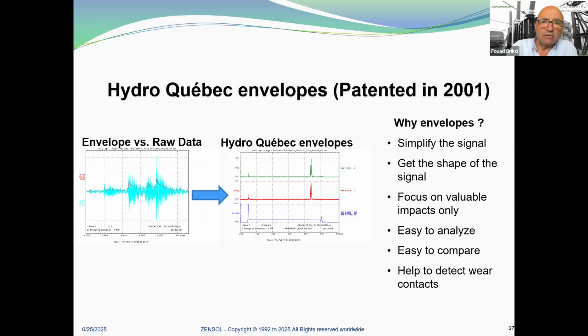Hydro-Quebec envelopes, patented in 2001. On the left, you can see the raw data of an accelerometer signal with the envelope superposed. Hydro-Quebec envelopes have been patented by Hydro-Quebec in 2001. And on the right graph, you can see the envelopes for the current and the high frequency and low frequency envelopes. So why envelopes? It simplifies the signal, gets the shape of the signal, focuses on valuable impacts only, is easy to analyze, easy to compare, and helps to detect worn contacts.